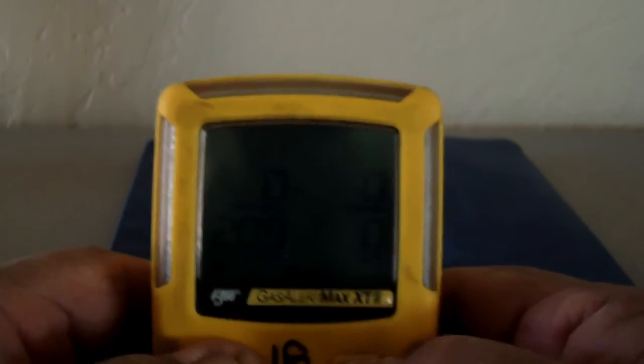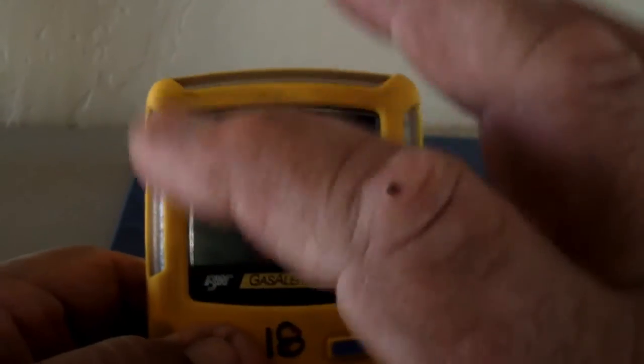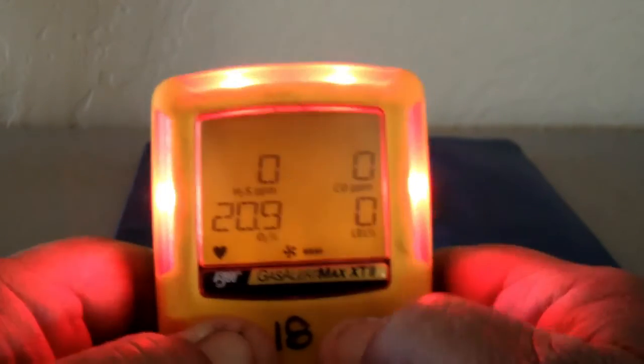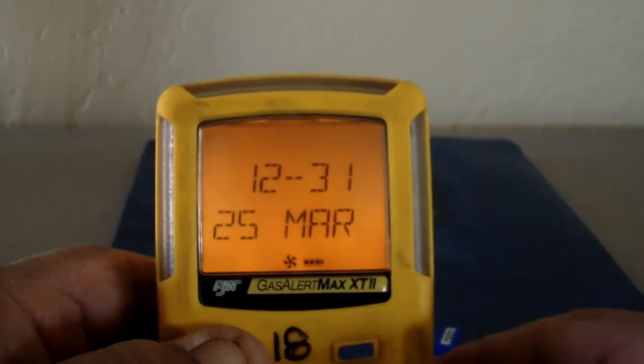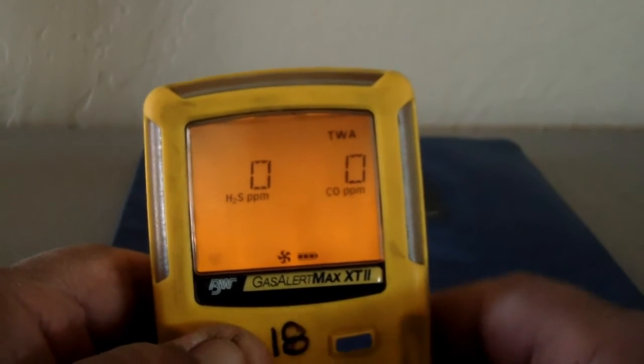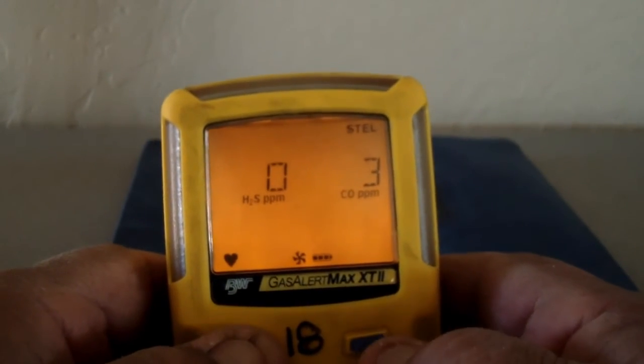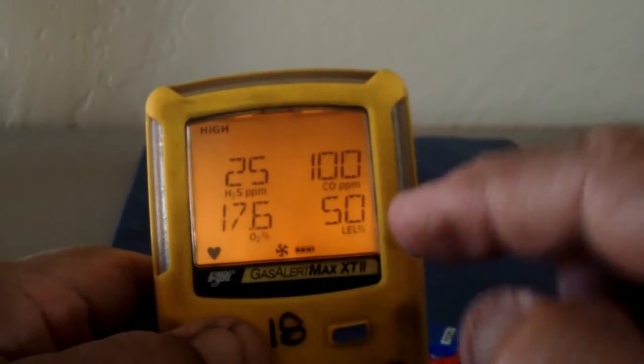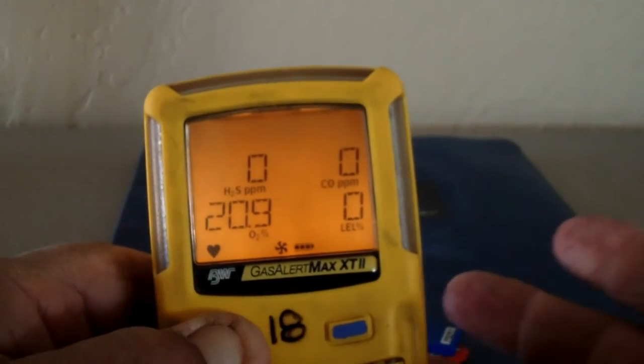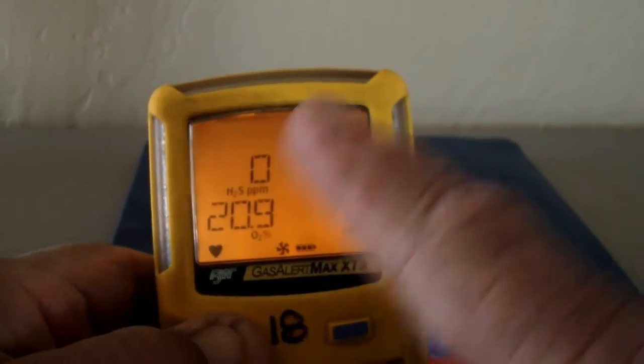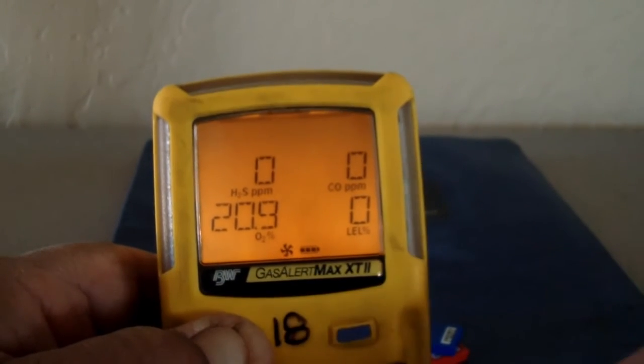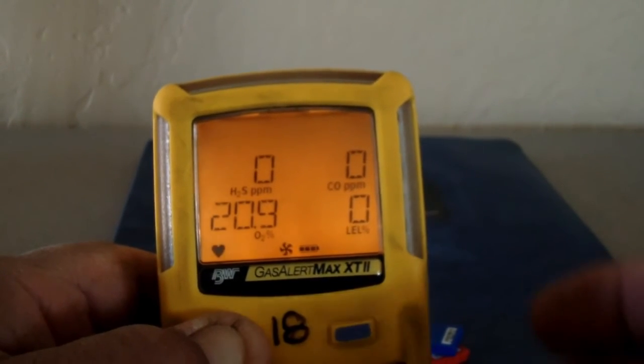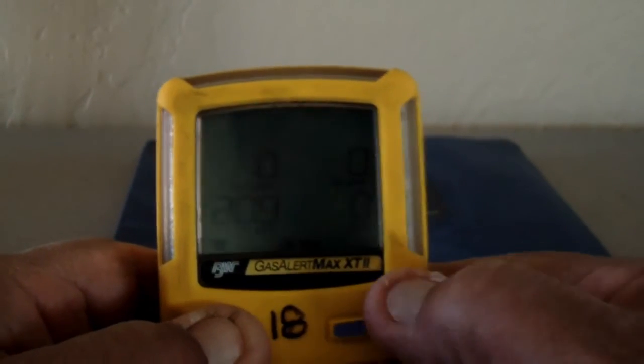So we talked about peaks earlier. At this point, I want to use that same button, and I'm going to test my peaks to see what the high readings on this meter are to this point. I push that twice quickly. It gives me the date, and it walks through. If I go into my STELs and TWAs, you can see some numbers there. This is the high that it read, and I wanted to clear all those out, so I just pushed the button. You're just following the screen to make sure everything is done properly. So once again, it's 2 quick pushes on the button, right?